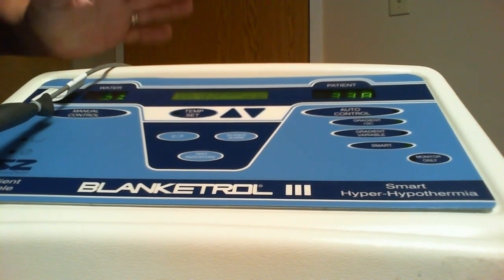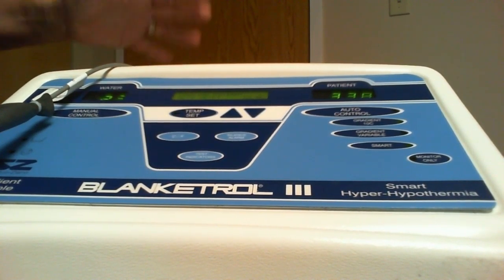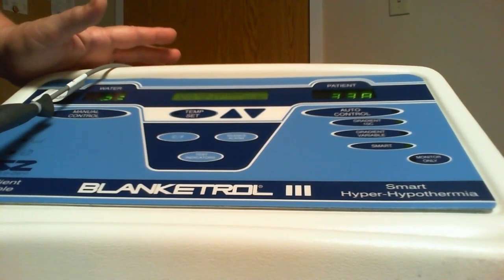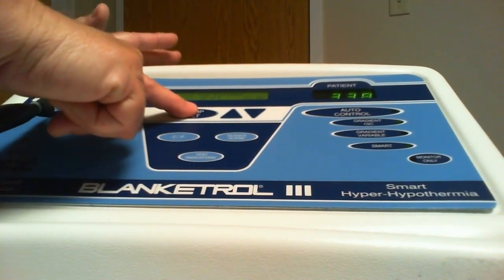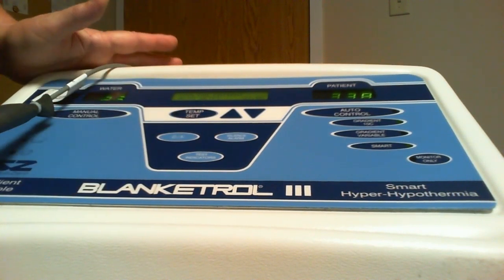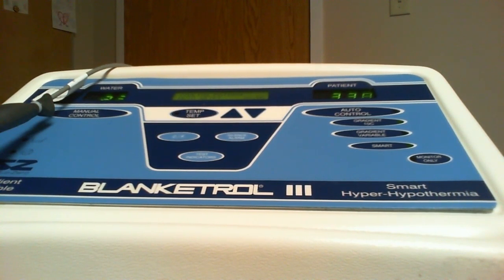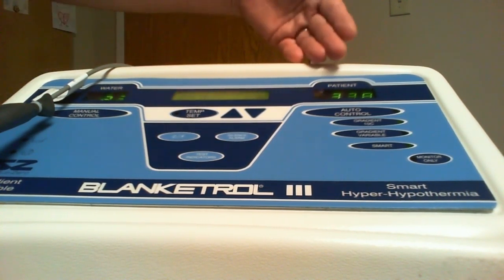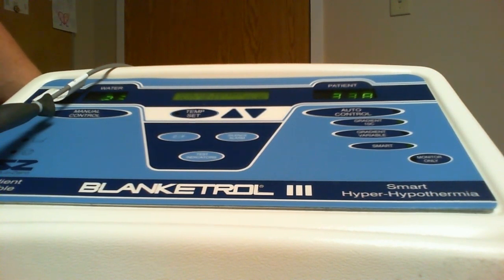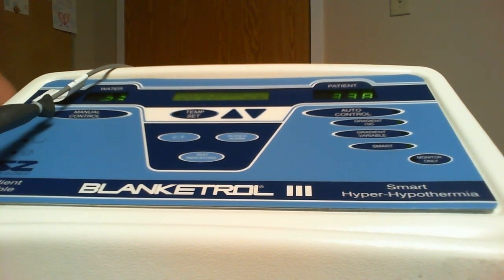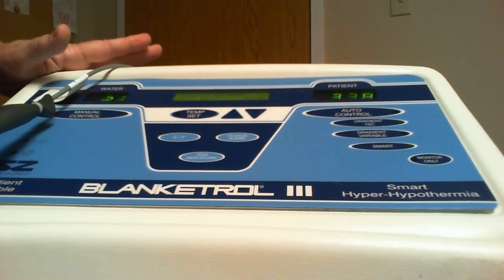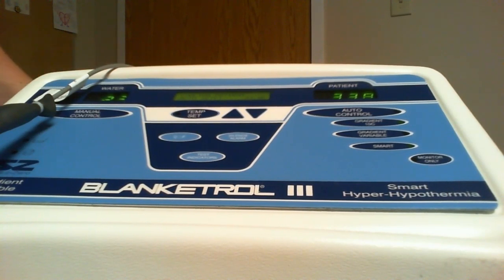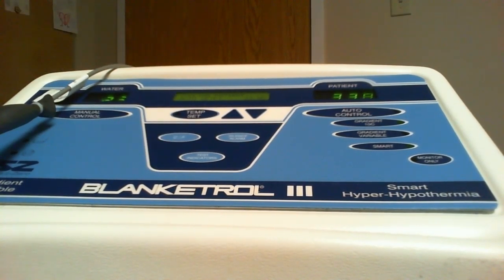And what that does is every 30 minutes, the machine takes a look at the patient's temperature and says, are we at temperature, at set temperature? If the answer is no, then the machine decides, do I have to warm the water or cool the water? And that will be dependent on what the patient's temperature is. If the machine has to warm the patient, then the water temperature will increase by 5 degrees. If the machine had to cool the patient, then the water would cool by 5 degrees. So it adds or takes away 5 degrees to achieve your set temp.